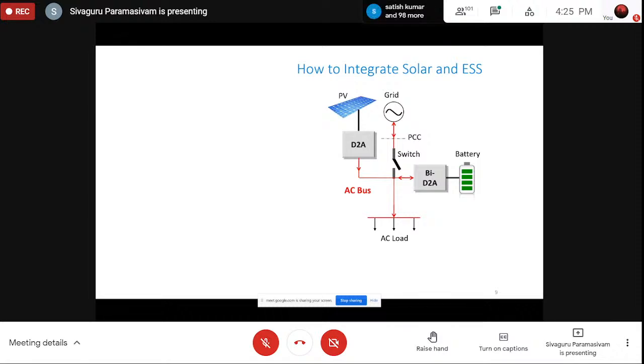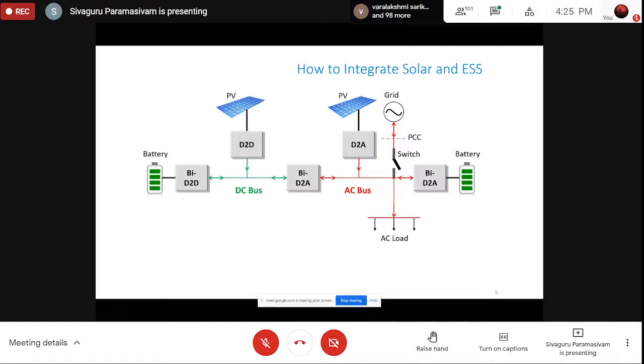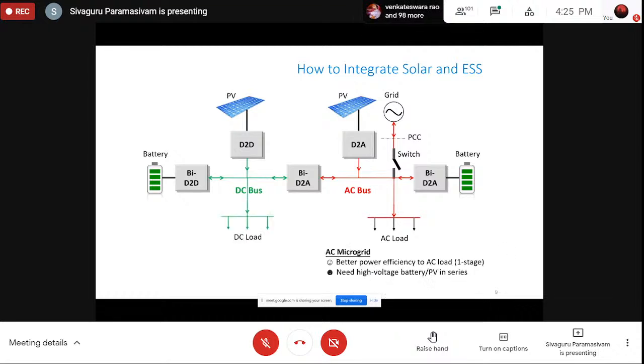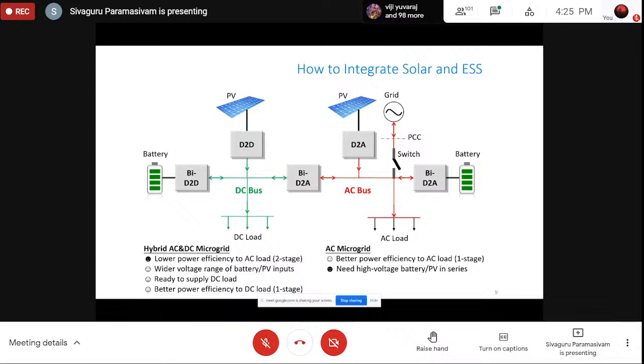When the PV is not available, the excess energy during the daytime will be stored inside the battery, and we can use the battery's energy or battery's power for the loads whenever there is no PV or even whenever there is no grid. So that's one more application in the schematic. And imagine that you have some DC loads as well. So we know that there are a lot of telecommunication systems that need only the DC load. So there will be DC SMPS, there will be a DC converter, and it needs only DC power. It doesn't need an AC power. So in that case, we can connect the similar system, and then we can directly provide that to the DC loads without the requirement of the DC to AC conversion.